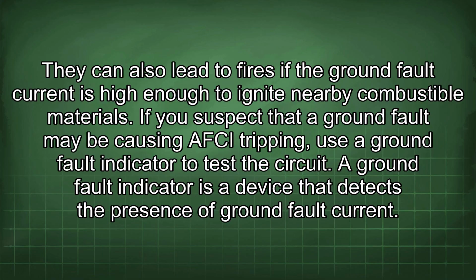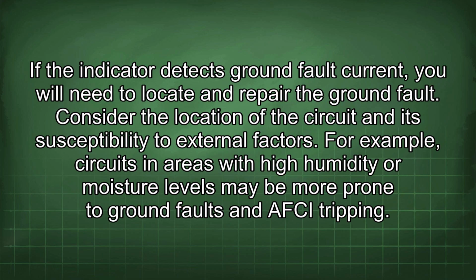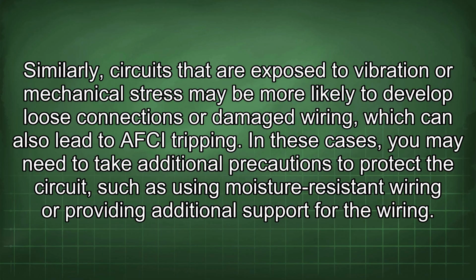If you suspect that a ground fault may be causing AFCI tripping, use a ground fault indicator to test the circuit. A ground fault indicator is a device that detects the presence of ground fault current. If the indicator detects ground fault current, you will need to locate and repair the ground fault. Consider the location of the circuit and its susceptibility to external factors. For example, circuits in areas with high humidity or moisture levels may be more prone to ground faults and AFCI tripping. Similarly, circuits that are exposed to vibration or mechanical stress may be more likely to develop loose connections or damaged wiring, which can also lead to AFCI tripping. In these cases, you may need to take additional precautions to protect the circuit, such as using moisture-resistant wiring or providing additional support for the wiring.